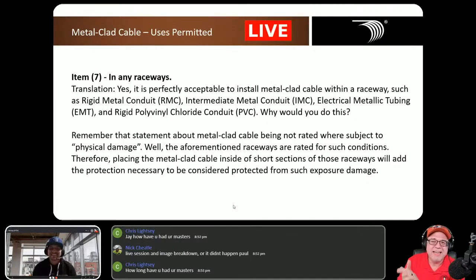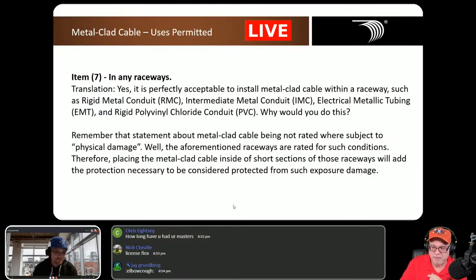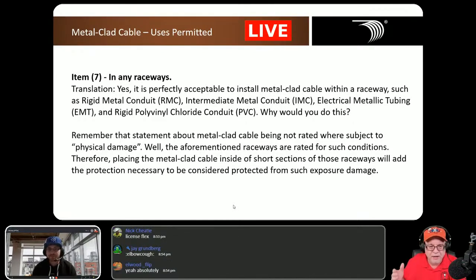So, in raceways — translation: can I put an MC cable inside a raceway? Absolutely, yes, especially if I need protection from physical damage. If I have to worry about physical damage, then I want to run MC cable. But let's say I'm in an area where somebody says you can't use it, but I want to use it because it's quick and convenient, comes on big reels, comes pre-done so I don't have to pull wires later.